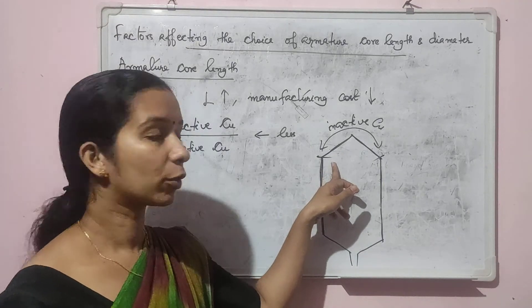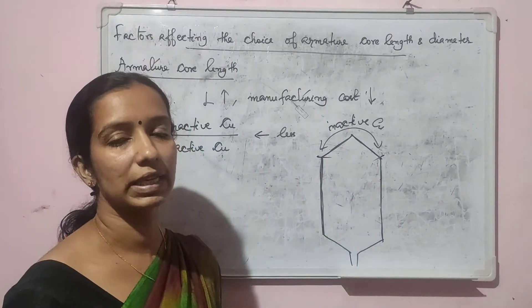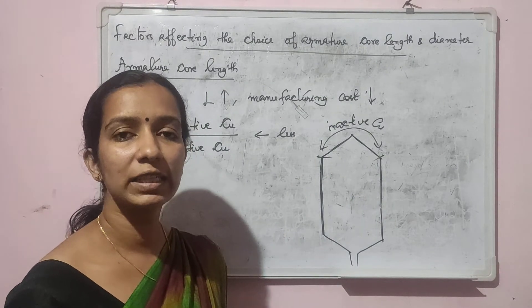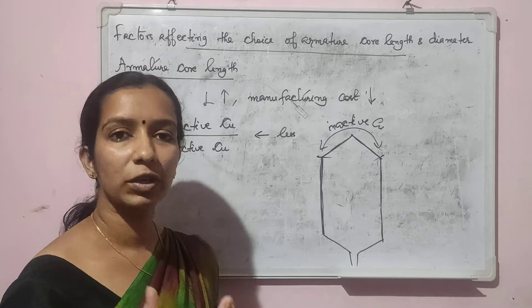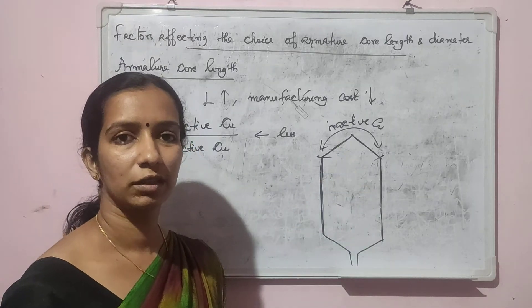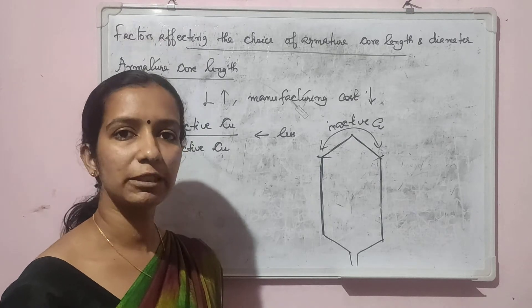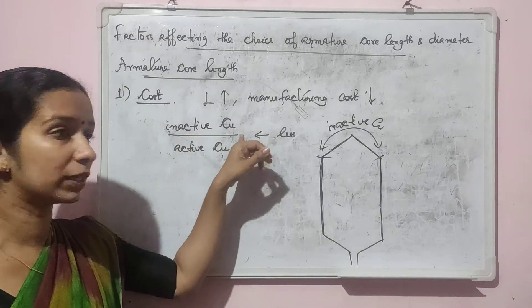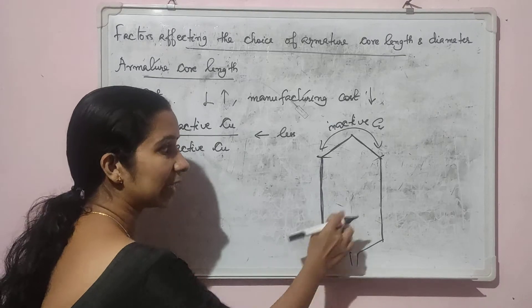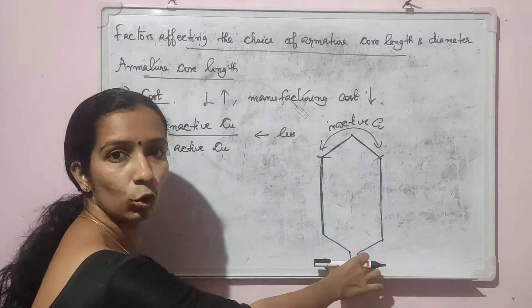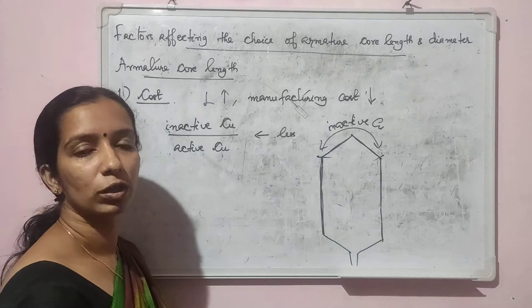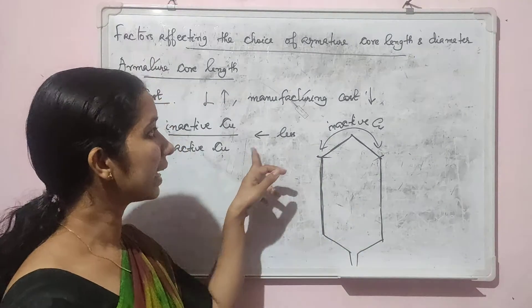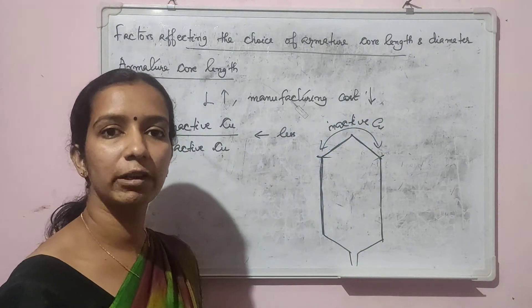The inactive copper is just for providing the end connection between the two coil sides. As this portion does not take part in EMF production, it is desirable to reduce the amount of inactive copper — if inactive copper is less, the machine will be cheaper. In a machine with a larger core length, the ratio of inactive copper to active copper will be less, and hence the machine will be cheaper with lower manufacturing cost.